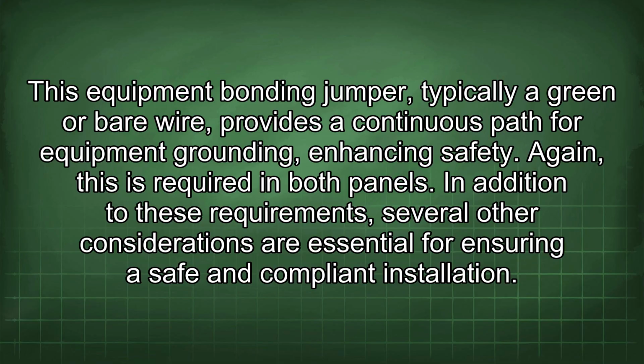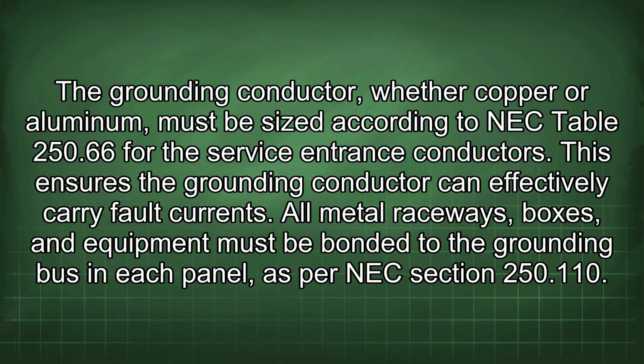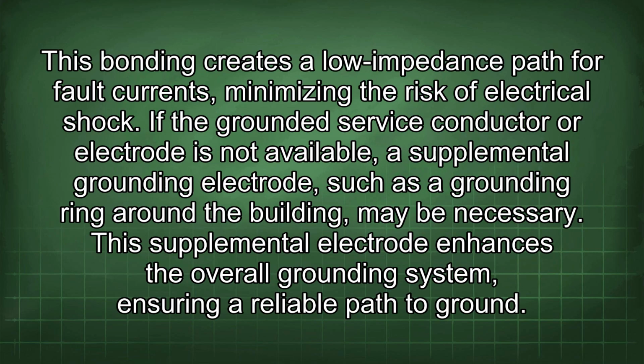In addition to these requirements, several other considerations are essential for ensuring a safe and compliant installation. The grounding conductor, whether copper or aluminum, must be sized according to NEC Table 250.66 for the service entrance conductors. This ensures the grounding conductor can effectively carry fault currents. All metal raceways, boxes, and equipment must be bonded to the grounding bus in each panel, as per NEC section 250.110. This bonding creates a low impedance path for fault currents, minimizing the risk of electrical shock.